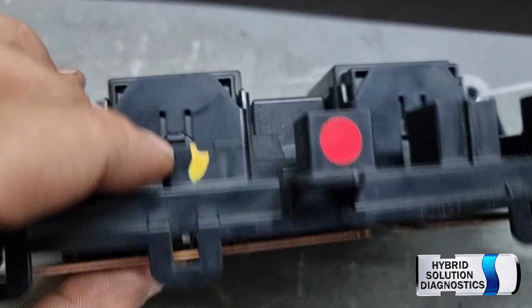So I can send positive, make the connection inside the relay, and then flow out to the positive outlet, which is this one. So you can now understand how the current flows in or out of the high voltage battery, but it needs to pass through these high power relays or contactors. It doesn't matter what you call it, they're just relays.